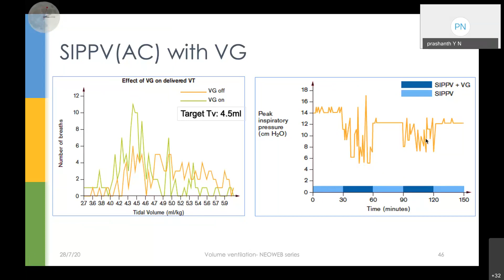Just as an example of another one, a baby is being ventilated with SIPPV, and intermittently we are adding VG. The dark blue ones show when the SIPPV was added with VG, and the lighter blue shows when the SIPPV was without VG. The y-axis shows the peak inspiratory pressure. When the volume guarantee was not there, the pressure required to deliver was much more. But when we add VG, the pressure required to deliver the volume goes down. The pressure is varying here, but it doesn't matter to the baby because pressure causes less harm to the baby than volume.